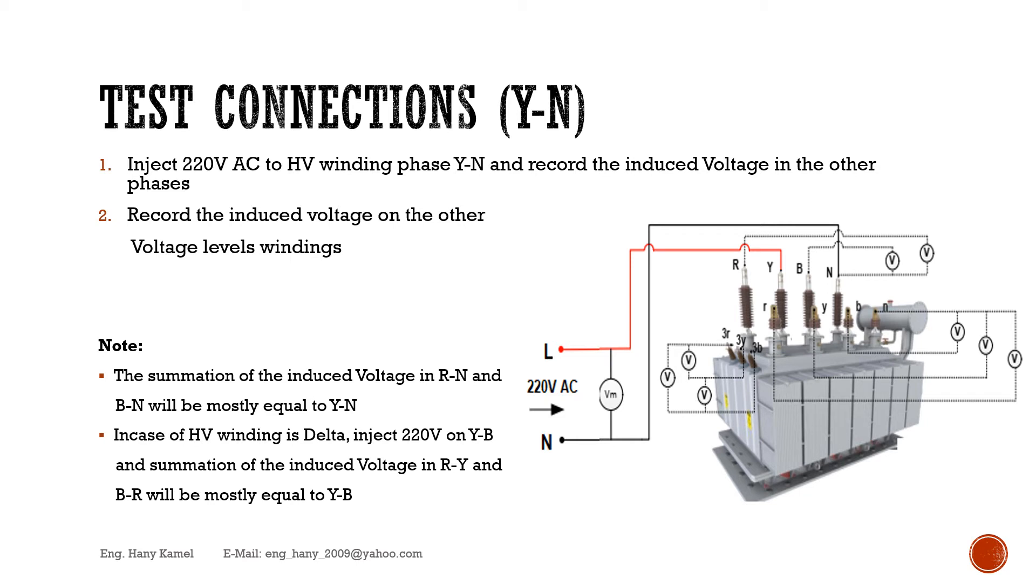Inject 220 volts on Y-B and summation of the induced voltage in R-Y and B-R will be mostly equal to Y-B.